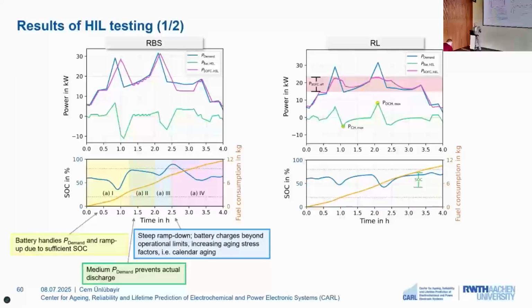Then we can see an interesting phase, highlighted here in blue. We see a steep ramp down, which is actually one of the critical phases of the SOFC, where the battery needs to be charged in order to compensate. We can see here that the battery is charged slightly above the limits we have set, so this is somewhat critical. Then the ramp down phase is over, and the high state of charge of the battery leads to a discharge again to level out and remain in normal operation.